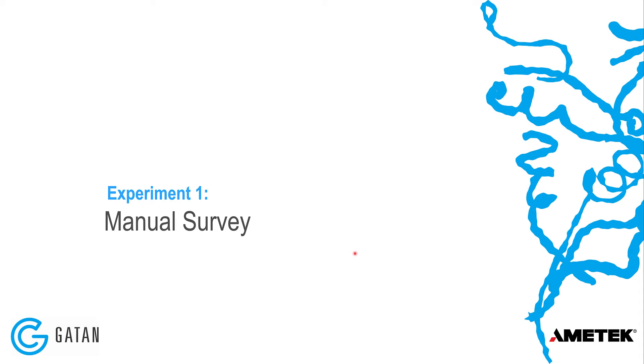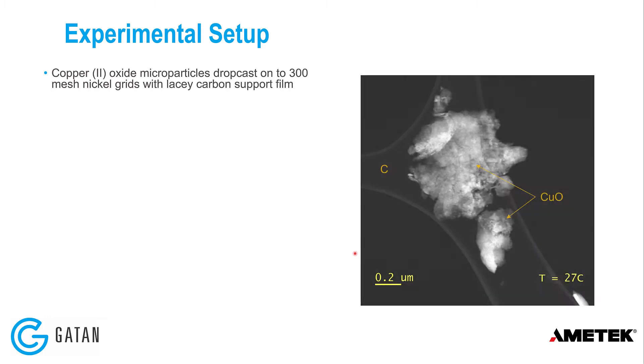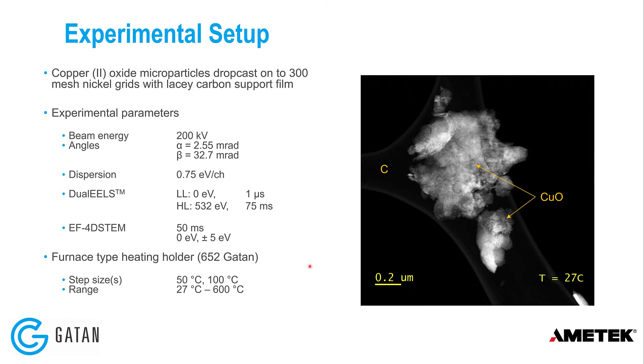The first experiment is a manual survey, looking at copper oxide particles drop-cast onto 300 mesh nickel grids with lacey carbon support film. All data was acquired at 200 kV with a fairly small convergence angle — acquiring dual EELS and energy-filtered 4D STEM. The furnace heating holder was used with a coarse step size of 50 or 100 degrees Celsius, from room temperature up to 600 Celsius.